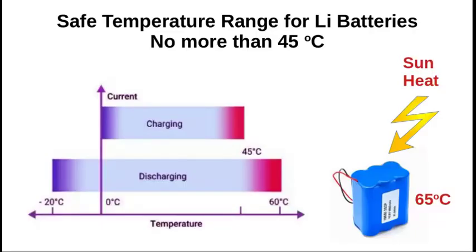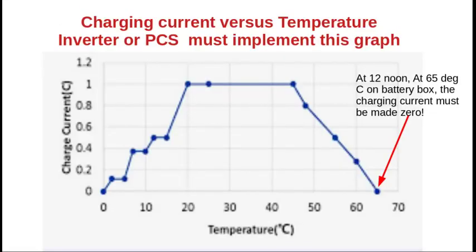The safe temperature range for charging of the lithium batteries is from 0 degrees C to 45 degrees C. For discharging, the safe temperature range is from minus 20 degrees C to plus 60 degrees C. This picture shows the current derating required when the lithium battery is charged. You see that the charging current should be derated, that is decreased, from 45 degrees C above, and the current must be made 0 at 65 degrees C.